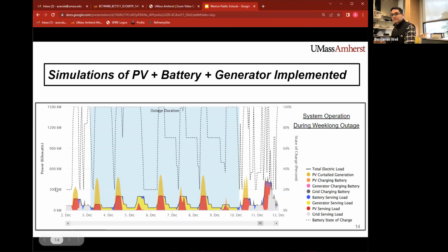This graph visually shows how the microgrid performs during the specified power outage. These yellow-orange peaks show when there is excess photovoltaic generation, the excess energy that is above what is needed by the load demands of the microgrid. This energy could be sent into additional storage mediums like additional batteries or that thermal storage. The yellow below the total electric load line, this black line, shows the total load for this outage, and the brighter yellow is when the diesel generator is working. So if you find a way to store this excess photovoltaic generation, you can even out these peaks and rely more on those cheaper, more resilient, renewable resources.